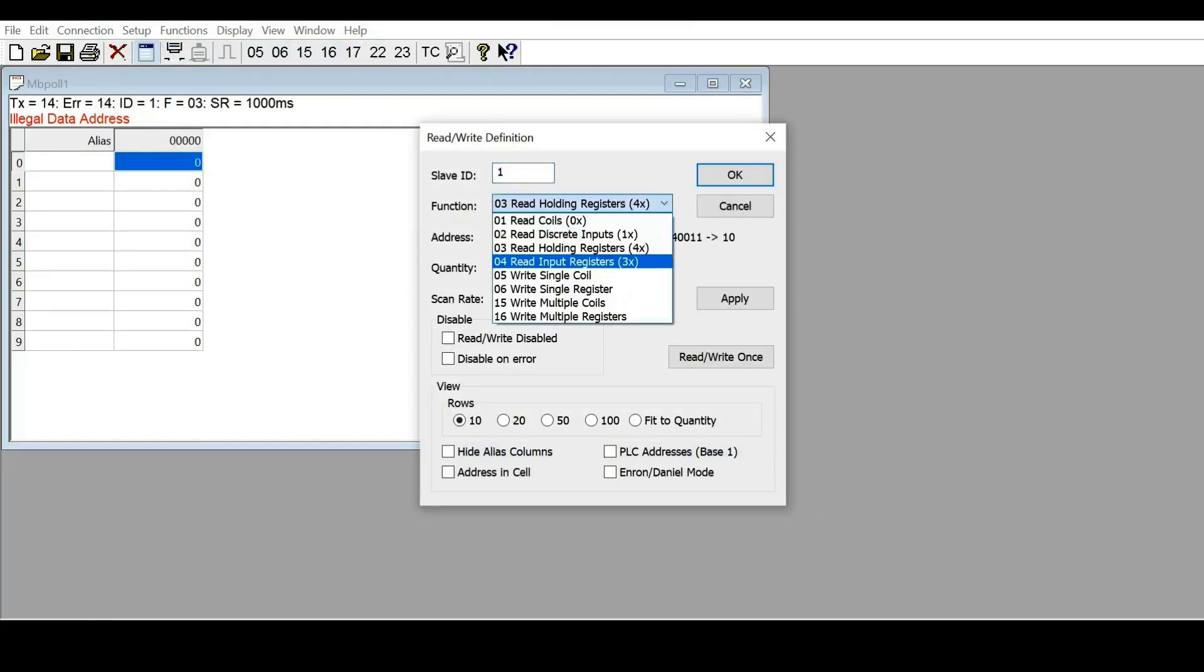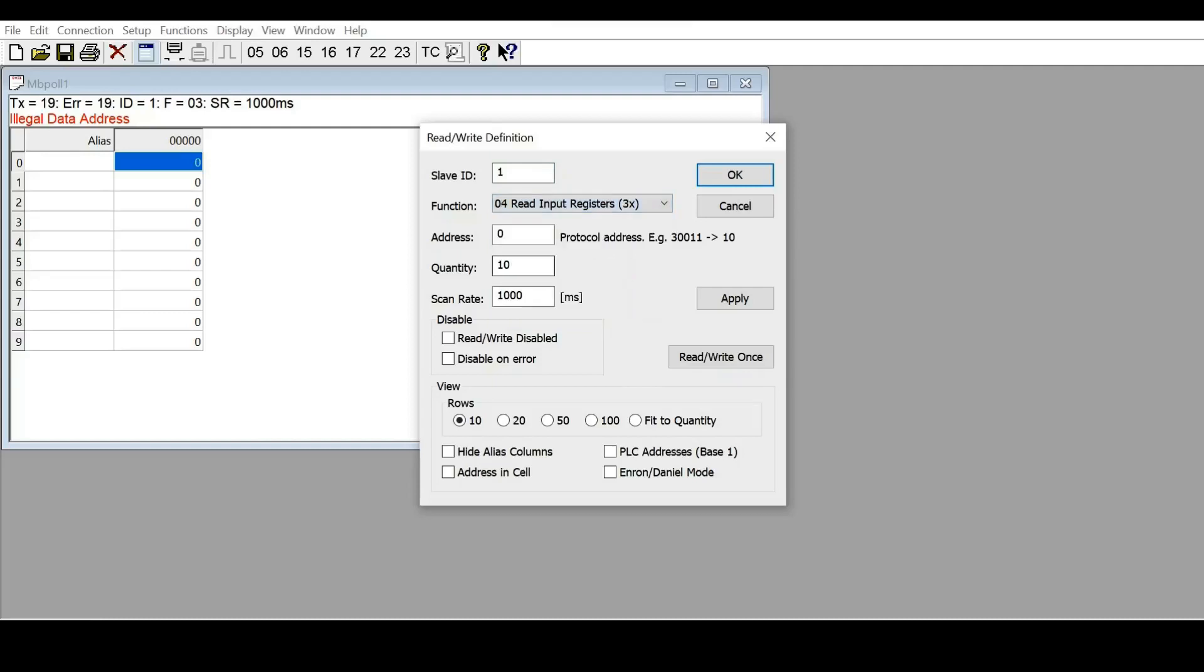Now, to show how to read the present value, it's a read input register. The address for the present value is 0, so we just need to read one point. I'll apply, and you can see the reading is 26. This is the reading on the controller.